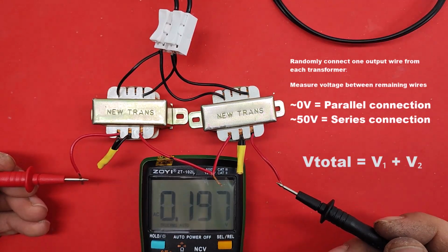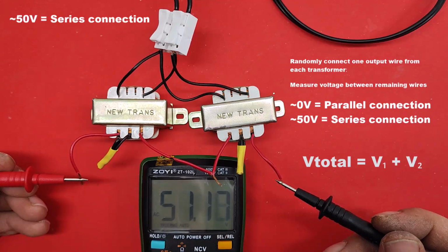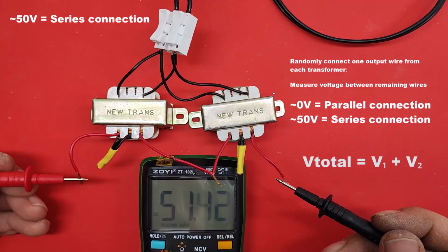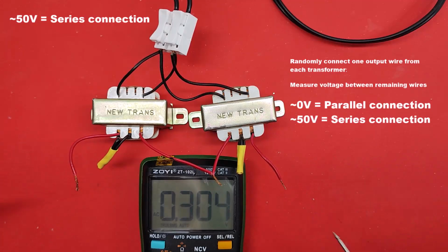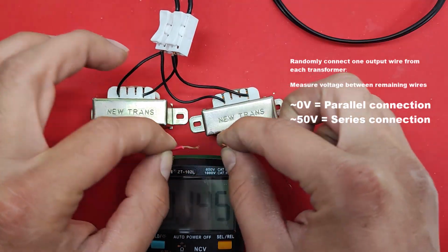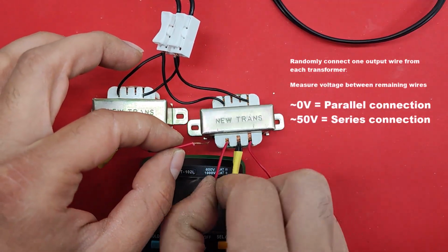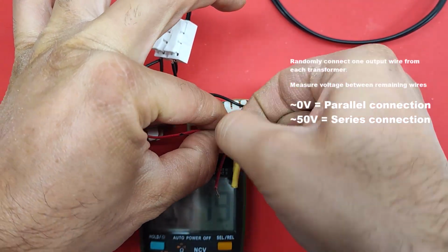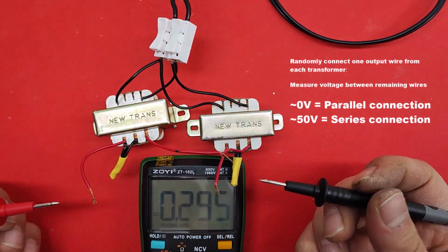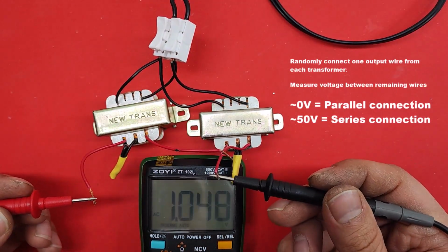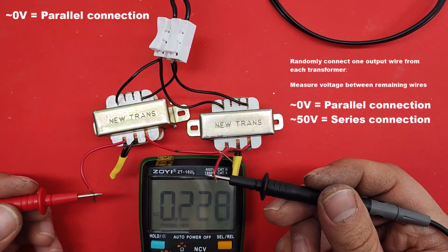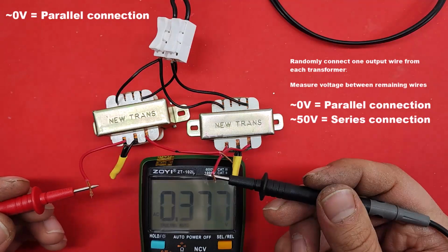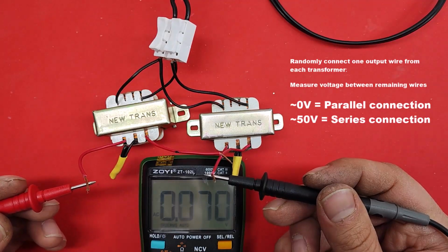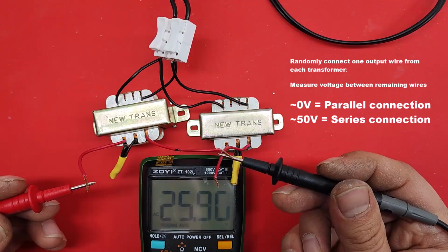If the measured voltage is close to double 24 volts, around 48 to 50 volts, this confirms a series connection. Now we swap one of the output wires. When the measured voltage drops close to zero, this means the transformer's outputs are 180 degrees out of phase. In opposite phase, voltages cancel each other instead of adding. This is not a fault, it's a phase reference issue.